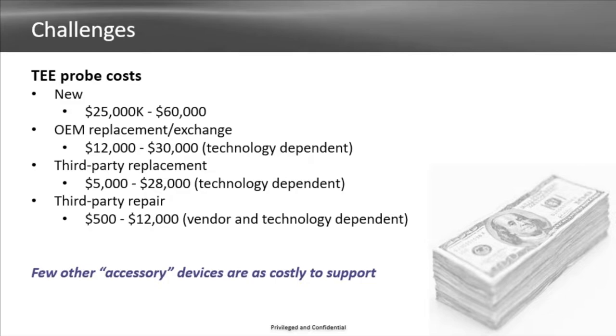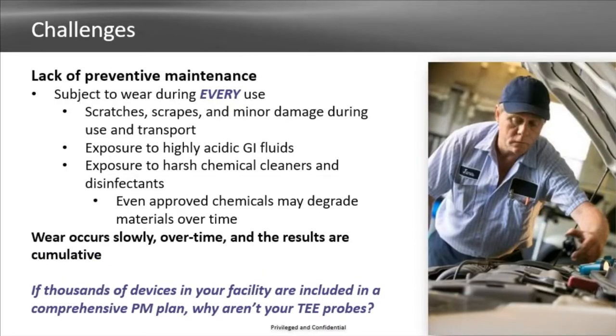A few other accessories, and we put accessory in quotation, are costly to support. This, the TEE probe, we intentionally put in quotes because this is not an accessory. A TEE probe is a class two medical device. It is a device in itself, not necessarily part of the ultrasound system as an accessory. It is its own class two device and has to be registered as a class two device with the FDA when they manufacture those.